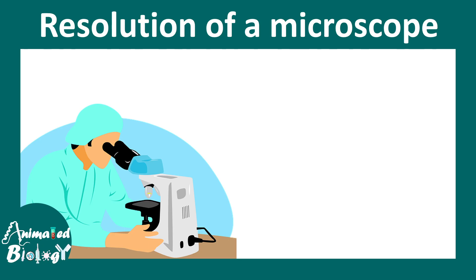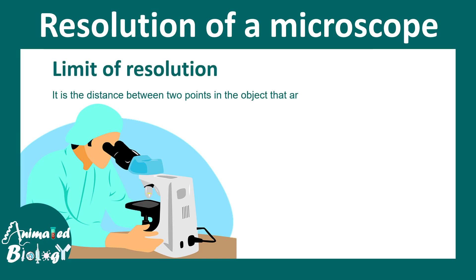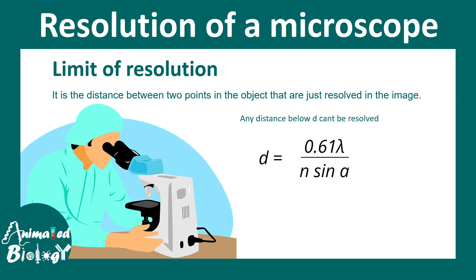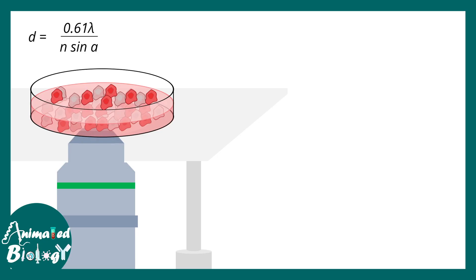The resolving power of the microscope is defined by a formula known as the limit of resolution. The limit of resolution is the distance between two point objects that are just resolved in an image, and it is given by: d = 0.61λ / (n sin α). Any distance below this d cannot be resolved, so the smaller the d, the better it is for a microscope.